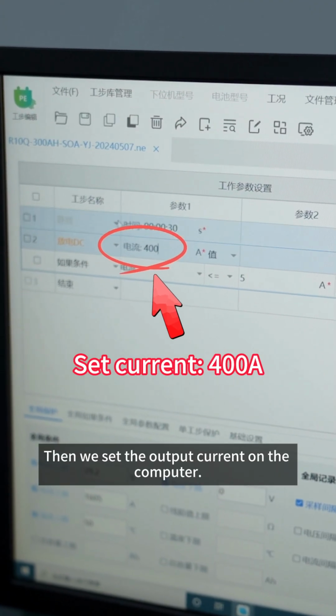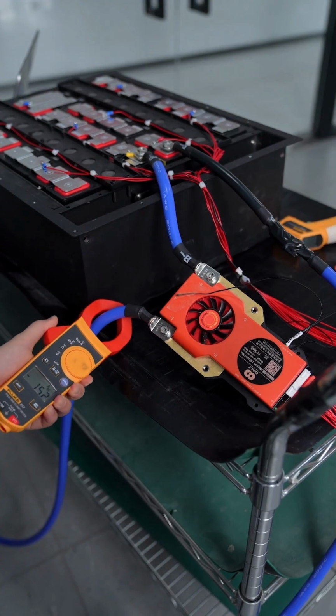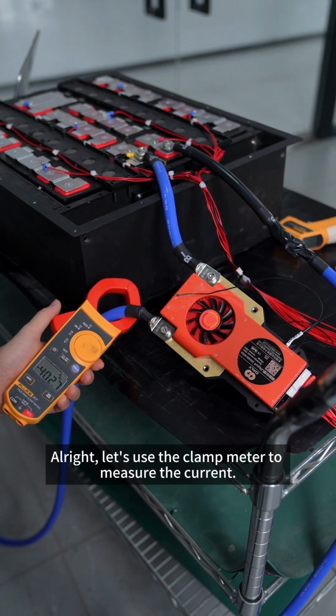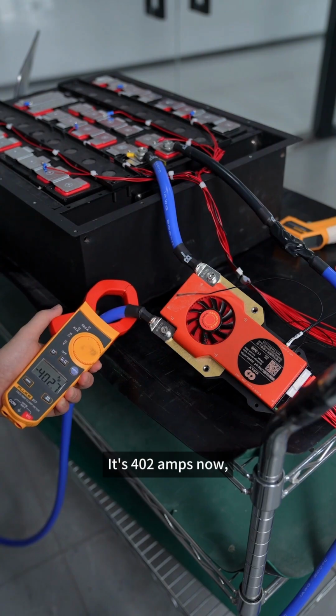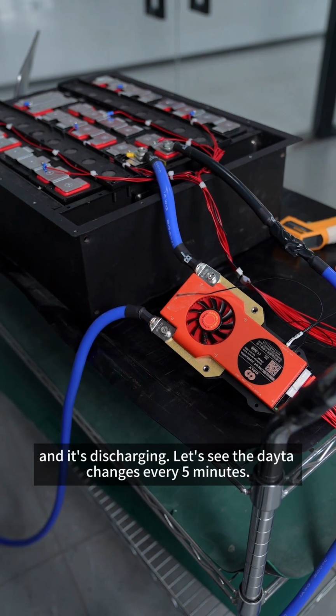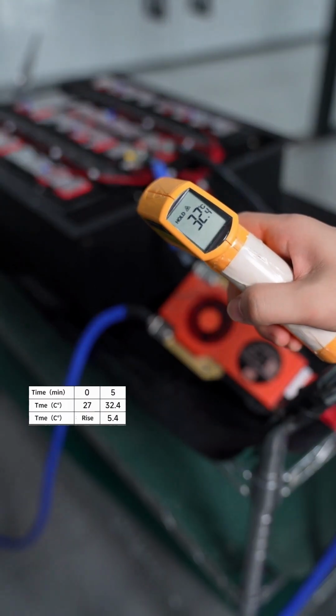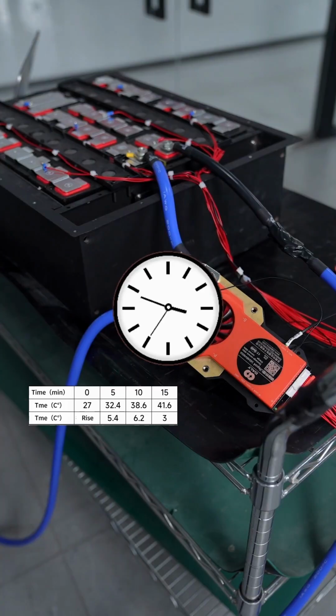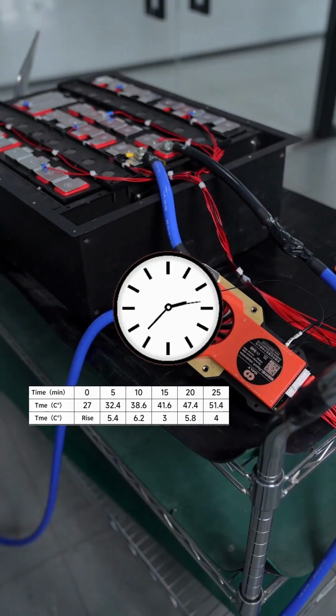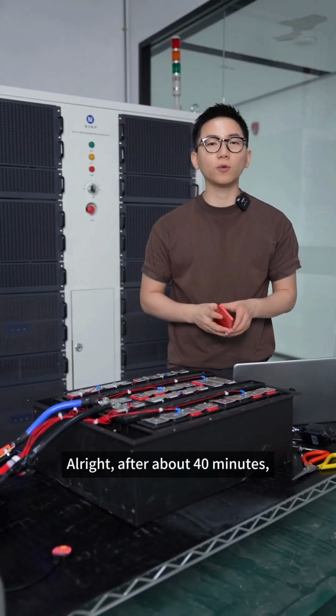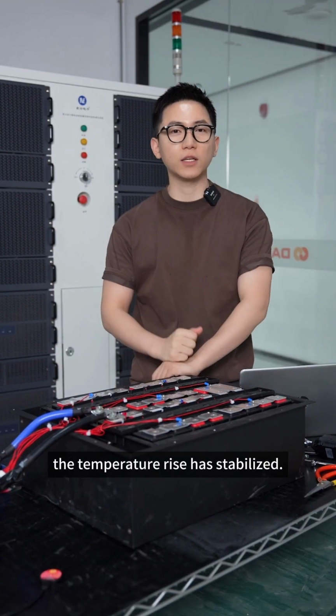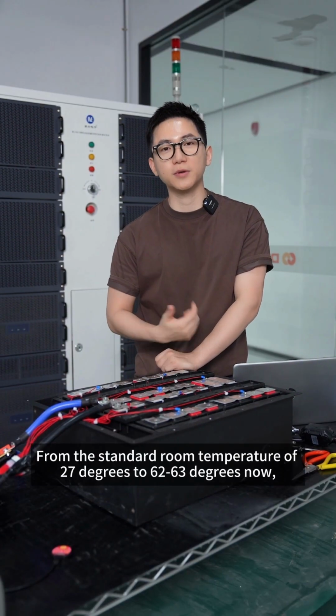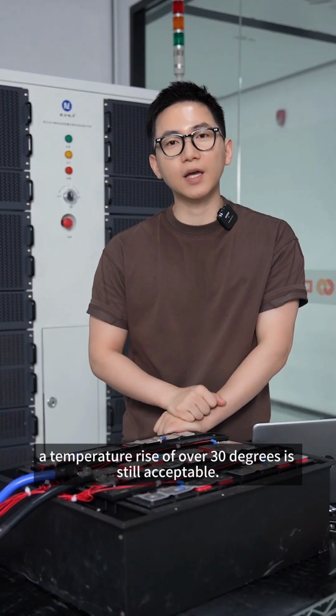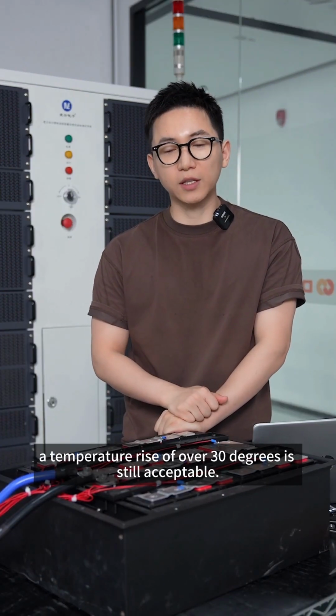Then we set the output current on the computer. Alright, let's use the clamp meter to measure the current. It's 402 amps now, and it's discharging. Let's see the data changes every 5 minutes. Alright, after about 40 minutes, the temperature rise has stabilized from the standard room temperature of 27 degrees to 63 degrees now. A temperature rise of over 30 degrees is still acceptable.